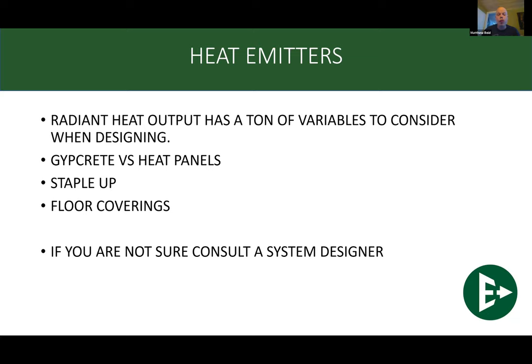And then finally, floor coverings. If I've got to heat through that subfloor and then I've got to heat through hardwood, that's going to be a different transfer of heat rate than if I'm doing subfloor and then tile. Tile is actually a pretty good conductor of heat, so we'd want to move that through. Clay is actually pretty decent at it. On the flip side of that, if I'm going subfloor and then a layer of foam and then a layer of carpet, carpet is super tricky to heat through. Not to mention that foam is in essence an insulator.